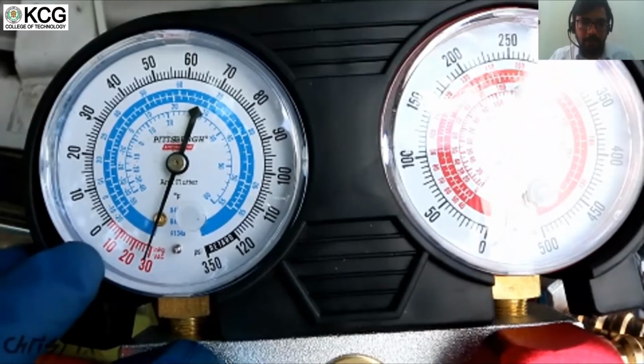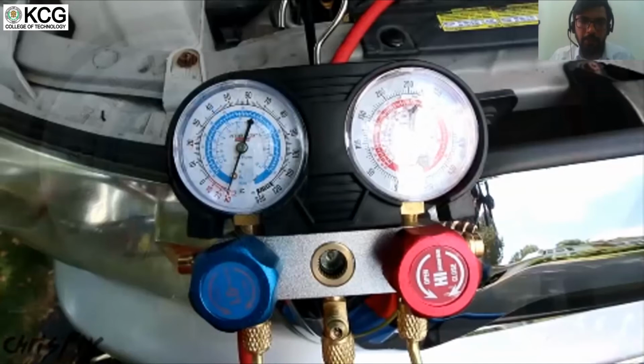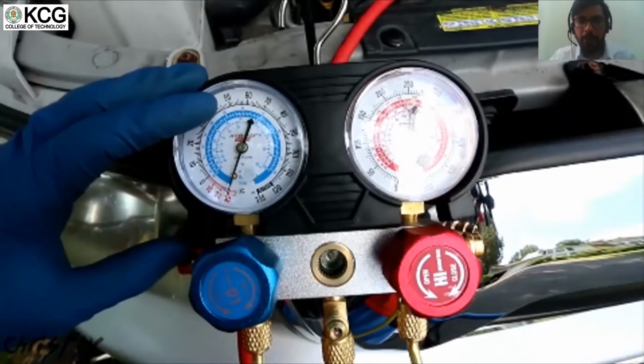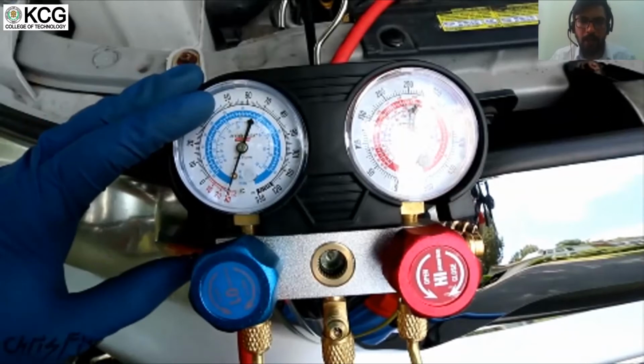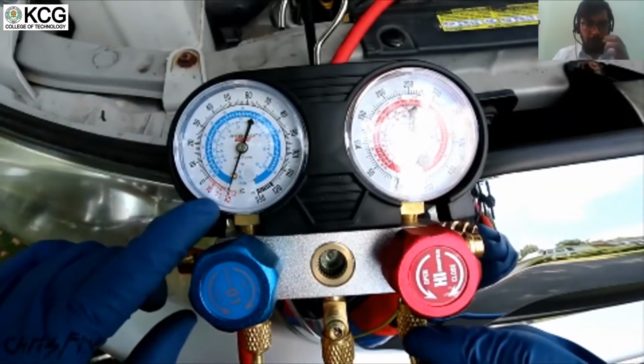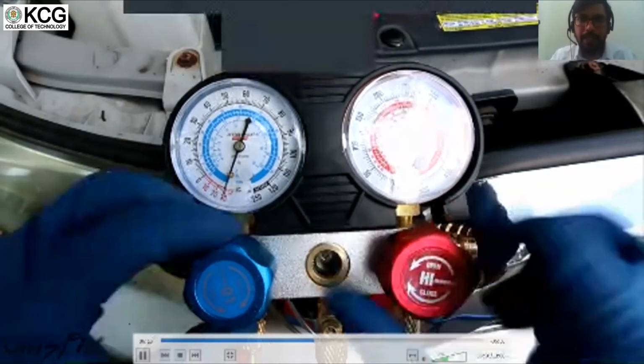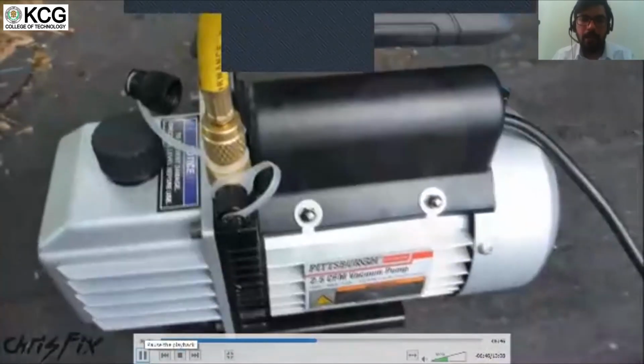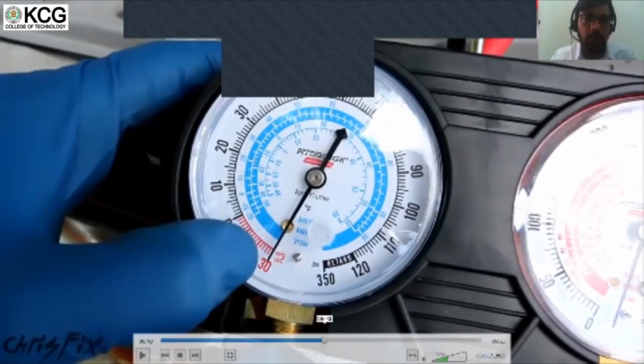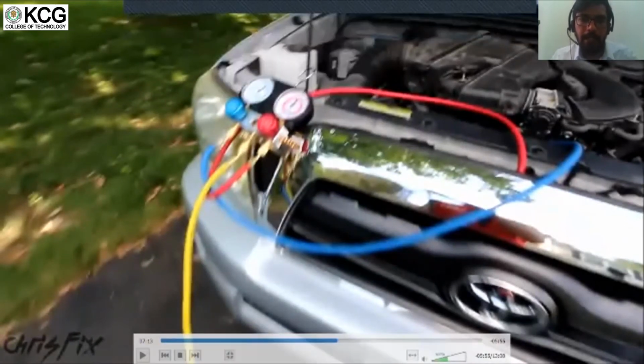I'm going to close these. So at this point of time, I'm going to close our vacuum pump. Inside the system, it should maintain vacuum for at least 1 to 2 hours. After you confirm that the vacuum stays inside the system, you have to run the vacuum pump for some more time so that there is no moisture inside the system, as moisture can highly damage your internal components. So make sure that you vacuum your system for at least a good 45 minutes. Once you do that, you have to start adding the refrigerant. So I'll start from that part.